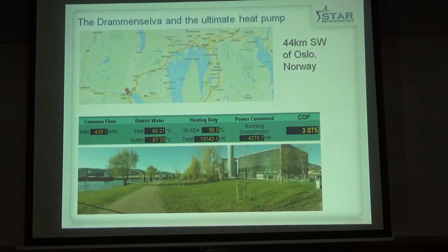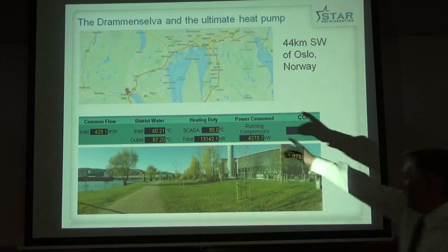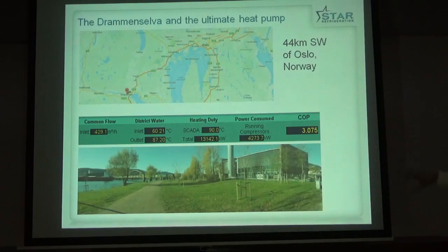And the Drammen project is on the banks of a river as well, the Drammenselva. It's about 45 kilometres southwest of Oslo. The river flows from the west here, and it flows out into the fjord. And this is the energy centre for the district heating system, and this is the river on the left-hand side of the photograph. The band in the centre is a screenshot from our site SCADA system. So you can see we're delivering 13.142 megawatts of heat. We're achieving a COP of 3.075 to do that. That was a kind of summertime condition.